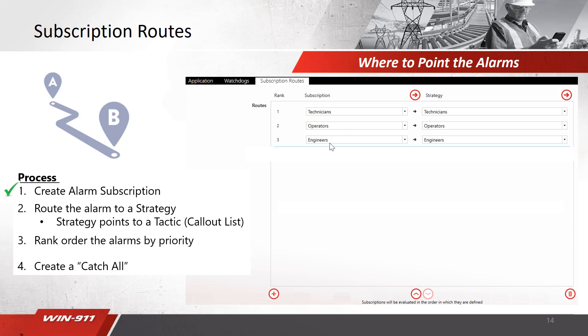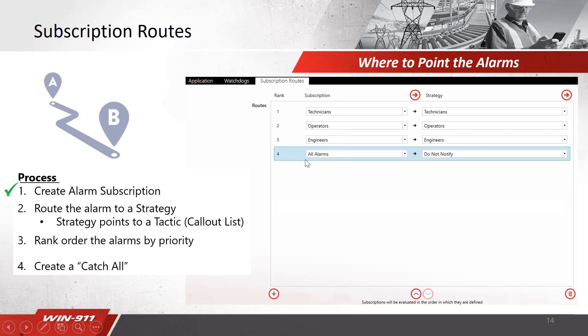To avoid that, we create an item called a catch-all. We create another filter at the very bottom called 'all alarms'. Alarms filter through 1, 2, 3, 4, and eventually get caught by this all alarms filter. You can point it to whatever strategy you choose — I chose to point it to a 'do not notify' strategy. I'll show you on the next few slides how you can use the Log Viewer as a troubleshooting tool.